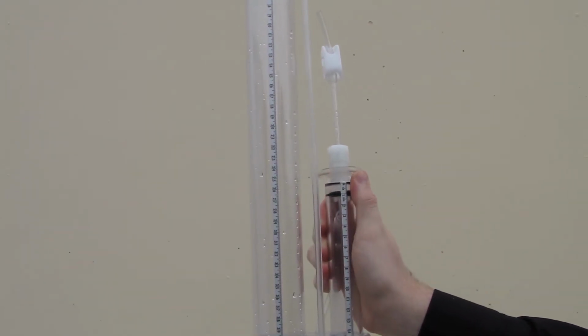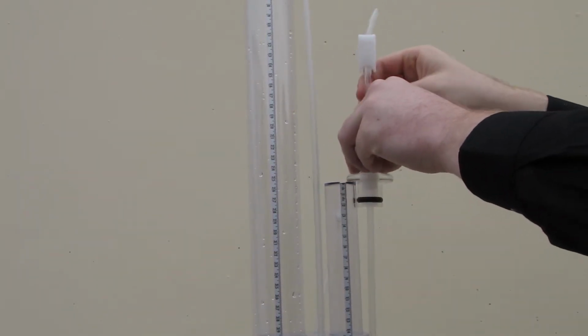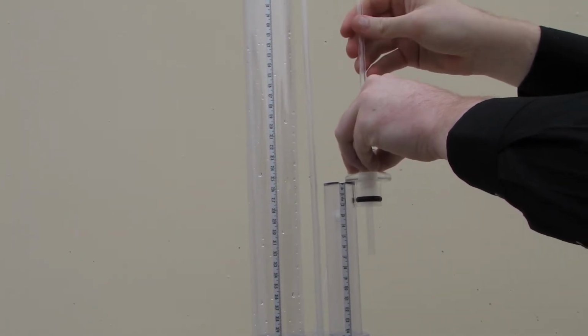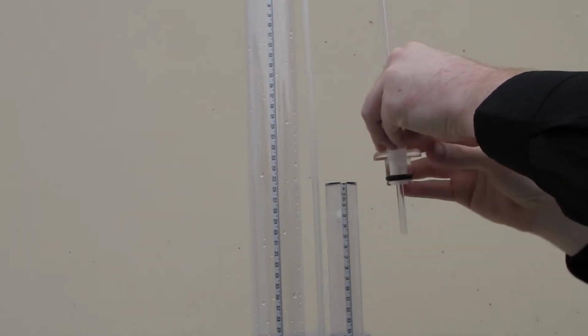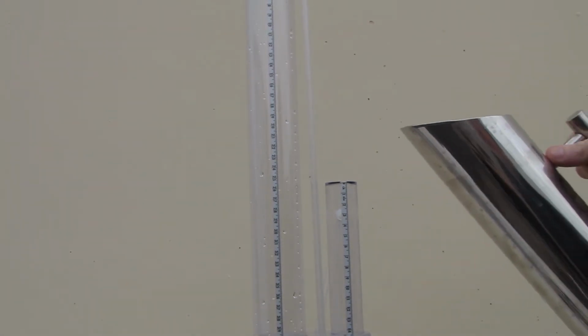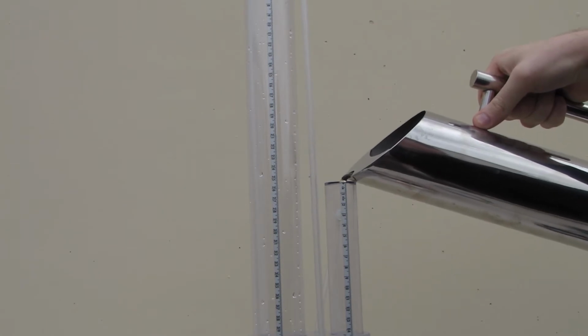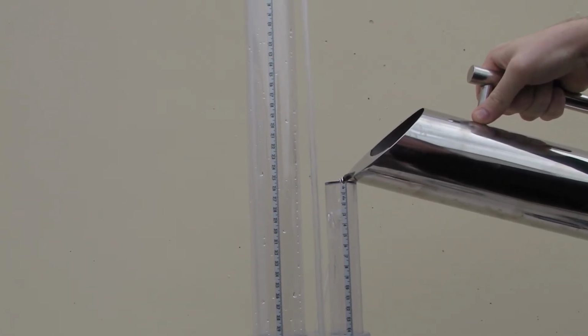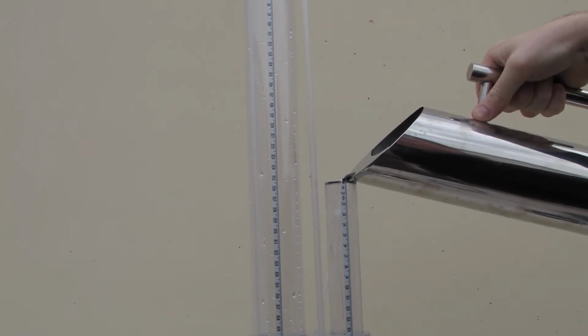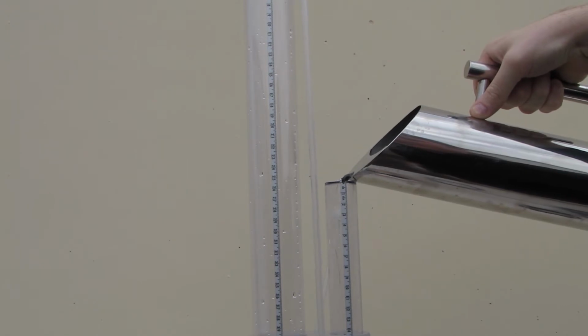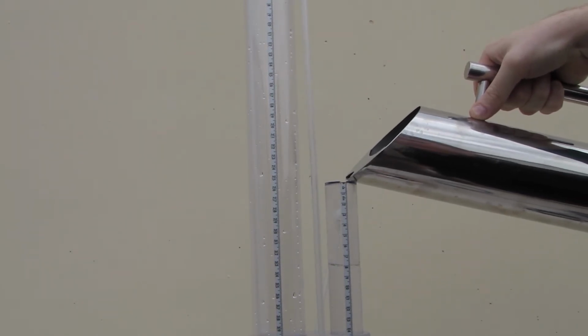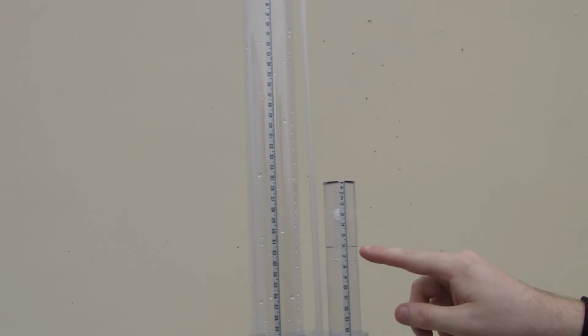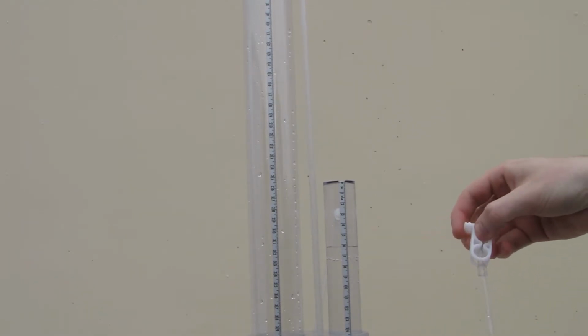Now it's time to fill the bubble tower. Start by removing the end cap with the inlet tube. Adjust the tube such that the end of it is equal to the 7 cm mark when installed. Next, fill the bubble tower with water to between the 6 cm to 7 cm mark. Open the clip valve, then reinstall the inlet tube and end cap assembly into the bubble tower.